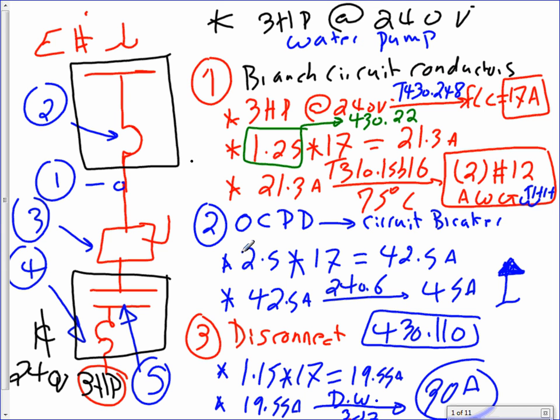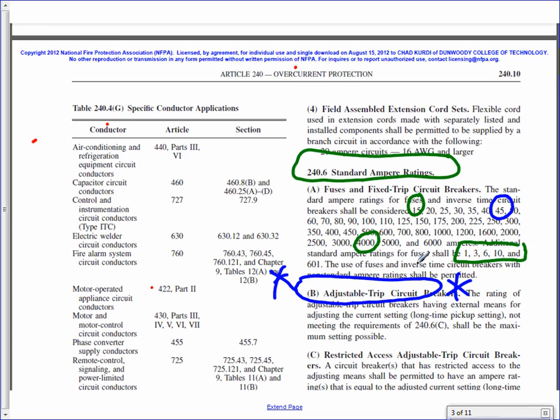So what do you do? Go call Warner Electric or Vikings or Graybar, order yourself a 30 amp 240 disconnect, throw it on the wall, and wire it. That's what people are going to pay you guys to size for them. All these sizes, you draw this line, you put the size in it, give it to a journeyman or a master, then they install it. Tell them what type of wire, EMT conduit we're going to use. Any comments, guys? Any questions about the first three? Should I move on? Okay, let's go to the next. We talked about these.